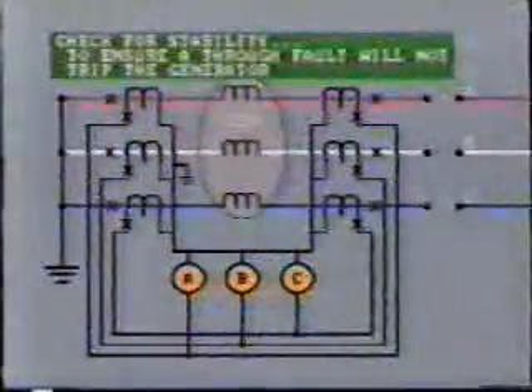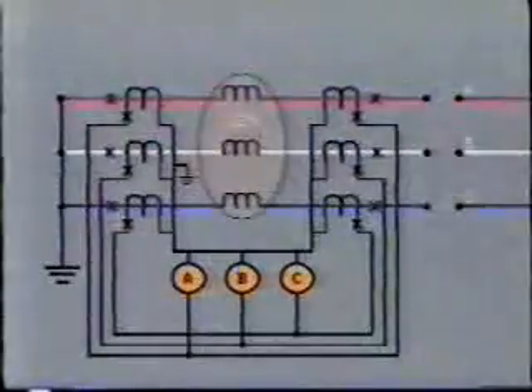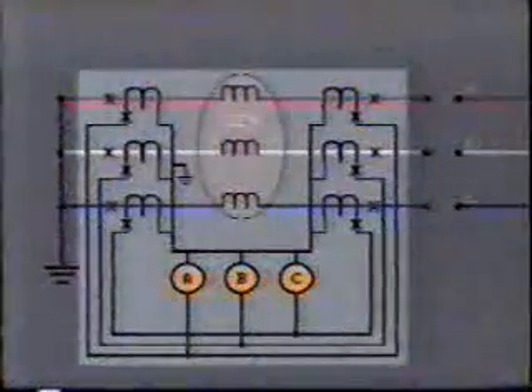But how can we check the differential relay for stability? That is to ensure that a through fault will not trip the generator. To do this, we need to check the interconnection of the CTs on either side of the generator. A convenient method would be to inject primary current from the test set and pass this through both sets of CTs, including the generator itself. However, it is probable that the test set will not have sufficient MVA capacity to overcome the impedance of the generator winding.